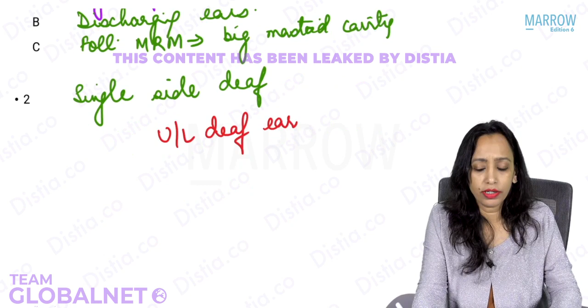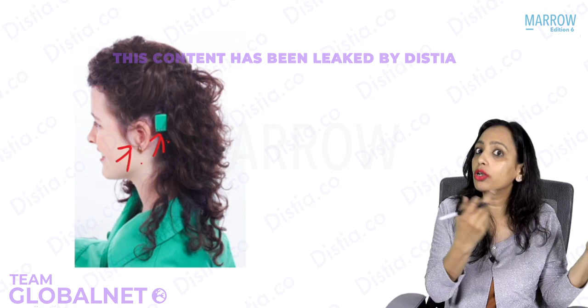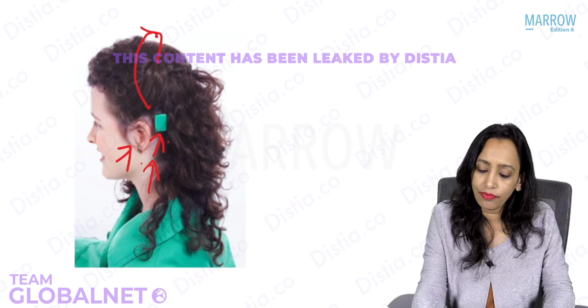It will collect the sound and it will vibrate the skull. When it vibrates the skull, it does not transmit sound only to this cochlea; the other cochlea also gets stimulated. So it will pick up the sound from this side and transmit it to the other side so that the other cochlea picks it up. So the patient will have better localization of the sound, a better three-dimensional perception of the sound. Even the sound coming from this ear will be perceived. So that is again another very important indication for Baha.